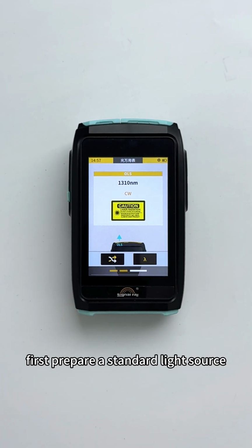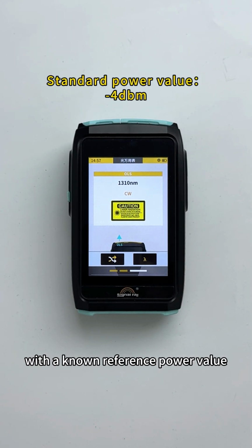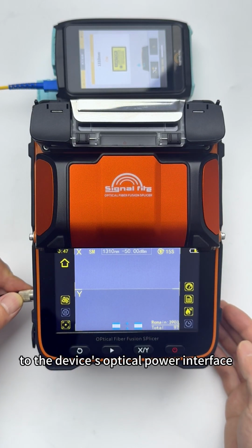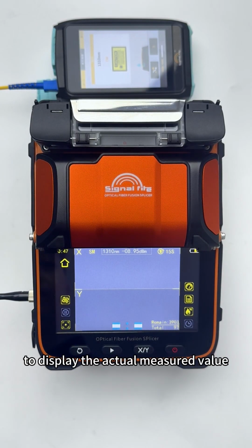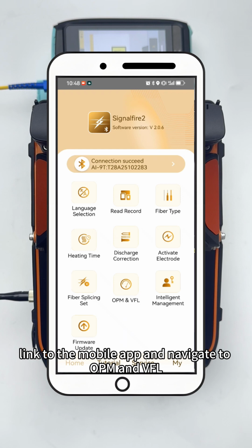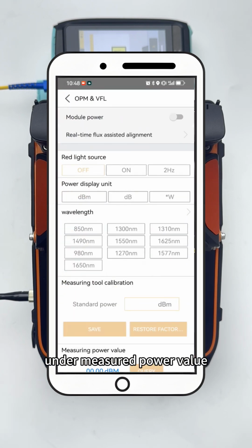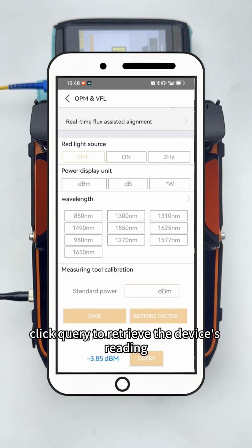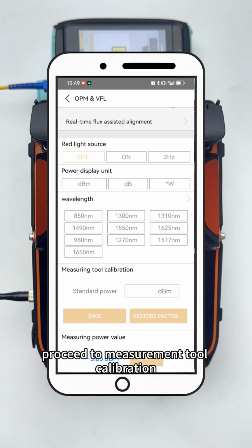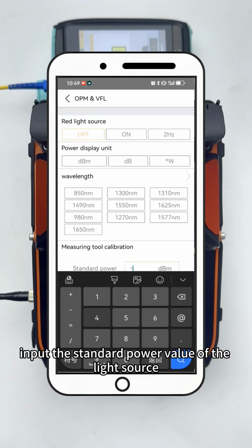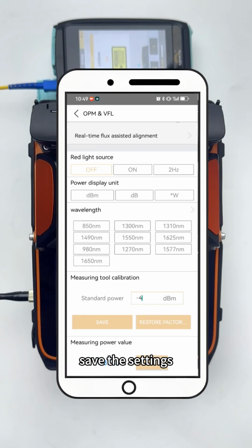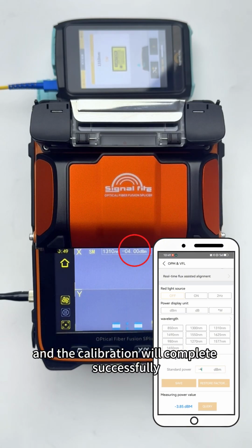First, prepare a standard light source with a known reference power value. Connect the standard signal to the device's optical power interface to display the actual measured value. Then, link to the mobile app and navigate to OPM and VFL under Measured Power Value. Click Query to retrieve the device's reading. Proceed to Measurement Tool Calibration. Input the standard power value of the light source, save the settings, and the calibration will complete successfully.